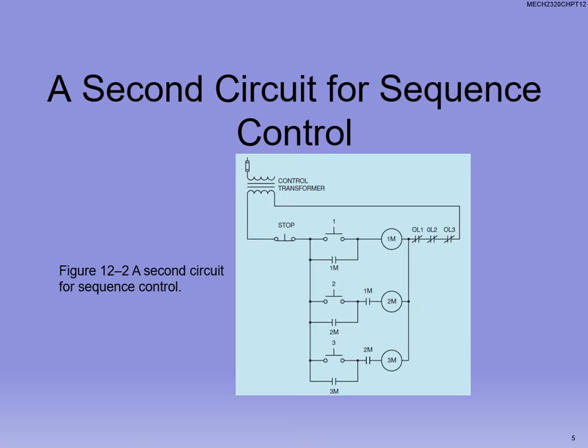We can also do something similar this way. Notice the difference — it's really where we've placed the contactors for 1M and 2M. We're still keeping 1M in parallel with push button 1 for the seal-in logic. But now, after push button 2 and before motor 2M, we've placed a contactor for 1M. That contactor will not close unless motor coil 1M is actually energized. Likewise, on the bottom line we put a normally open contactor for 2M in the 3M motor coil circuit, so 3M will not energize unless 2M is closed and push button 3 is closed as well.